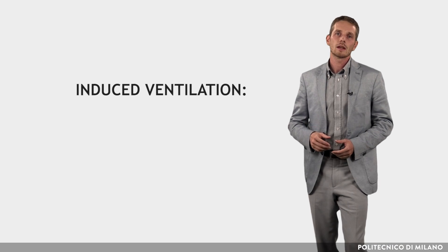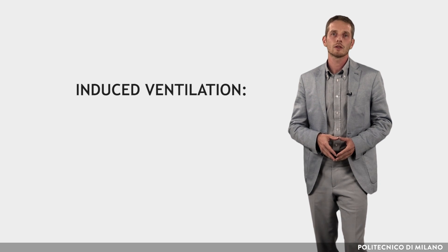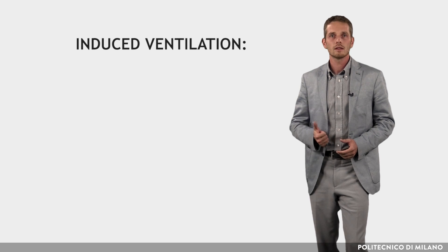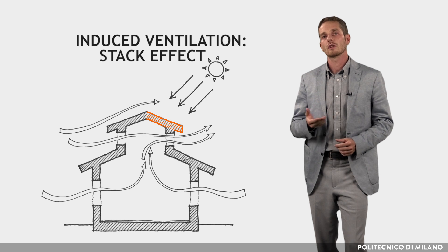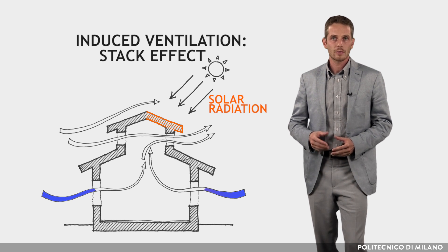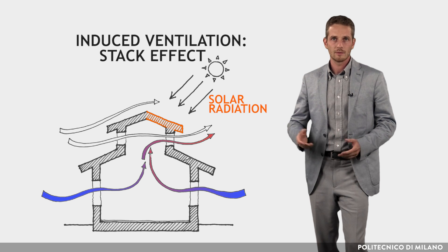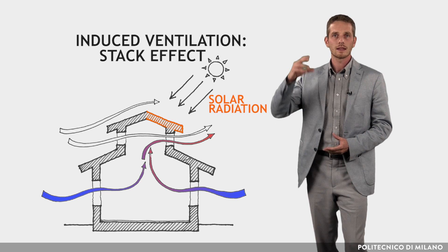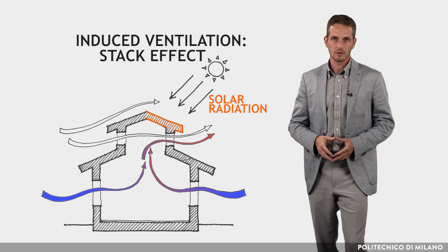Induced ventilation can be very effective in hot and humid climates as well as in hot and dry climates. Ventilation can be induced in three ways. One way involves heating air in a restricted area through solar radiation, thus creating a temperature difference and causing air movements as in solar chimneys. The draft causes hot air to rise and escape outdoors, drawing in cooler air and thereby causing cooling.